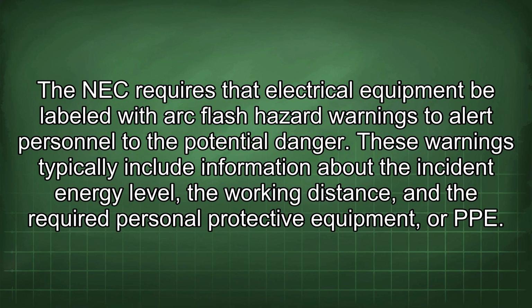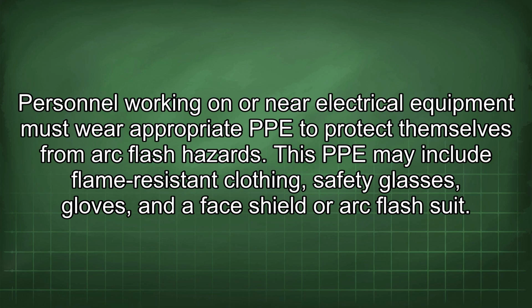The NEC requires that electrical equipment be labeled with arc flash hazard warnings to alert personnel to the potential danger. These warnings typically include information about the incident energy level, the working distance, and the required personal protective equipment, or PPE. Personnel working on or near electrical equipment must wear appropriate PPE to protect themselves from arc flash hazards.